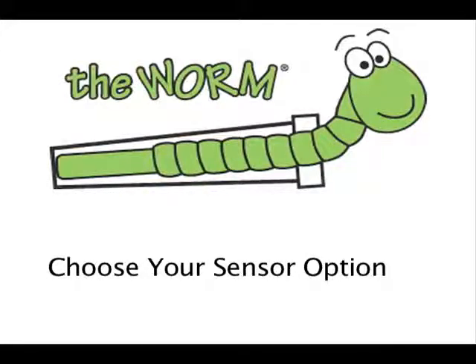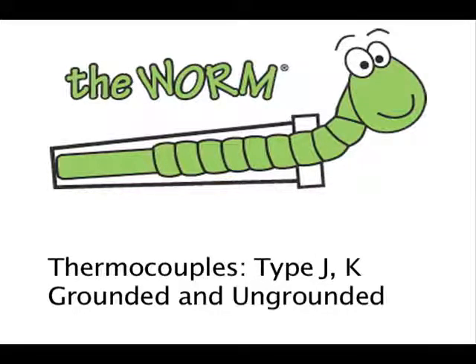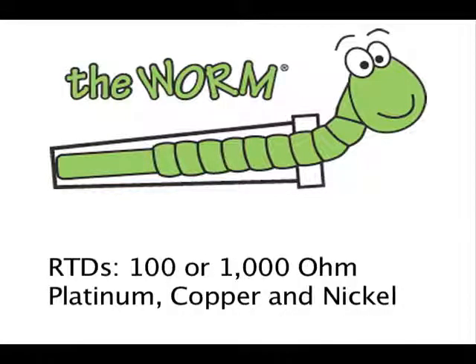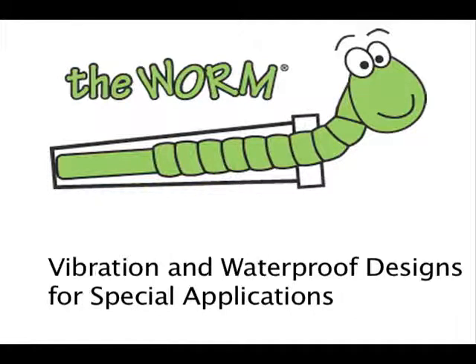Worms are available in quite a range of sensor types too. If you need thermocouples, there's a selection with types J and K being the most popular. Choose from standard and high temperature versions, both grounded and ungrounded. If you prefer RTDs, choose from 100 or 1000 ohm, standard and high temperature platinum, copper, and nickel. You can even get vibration-proof and waterproof designs if your process demands it.